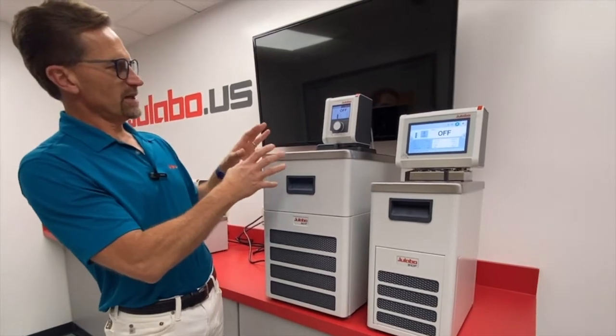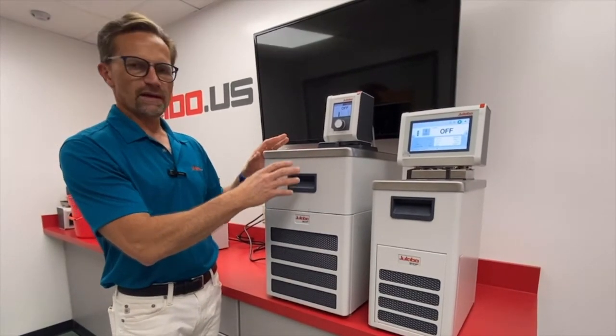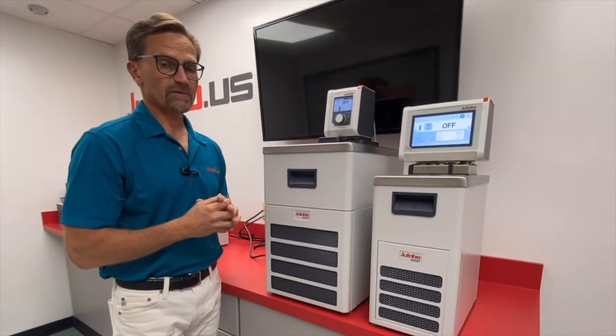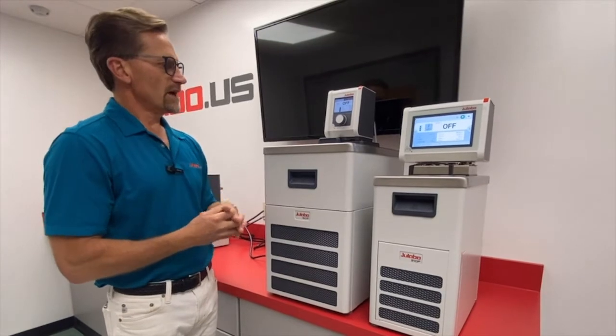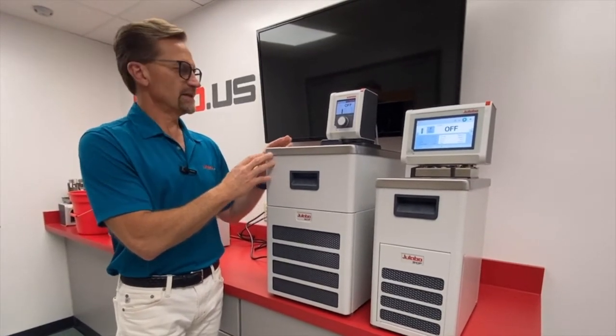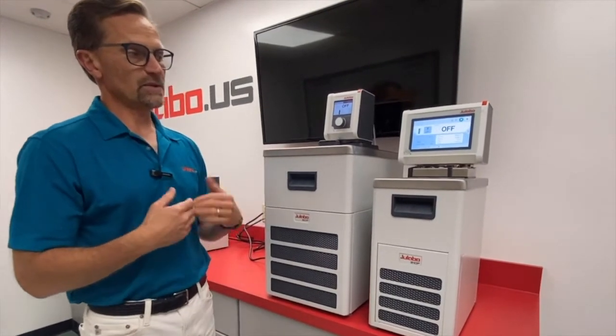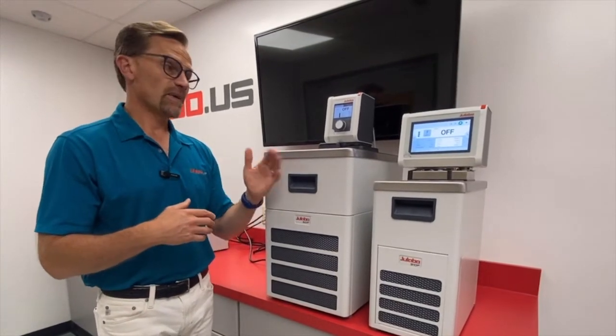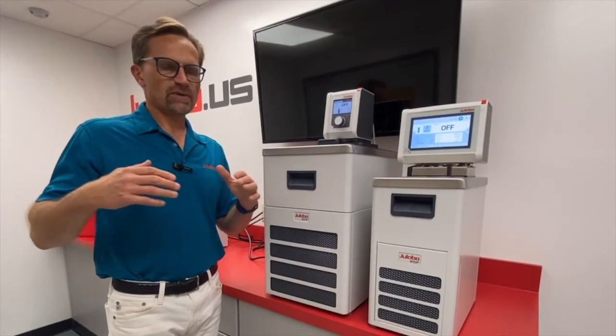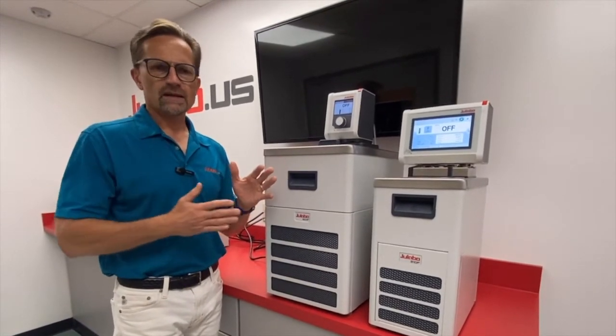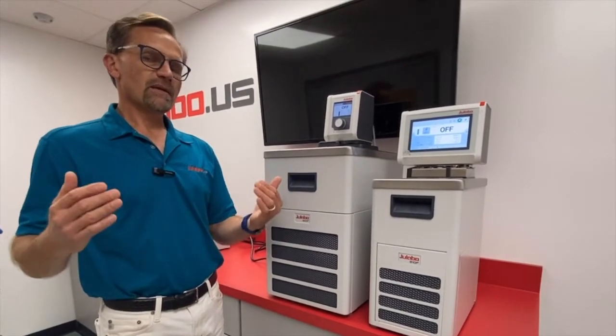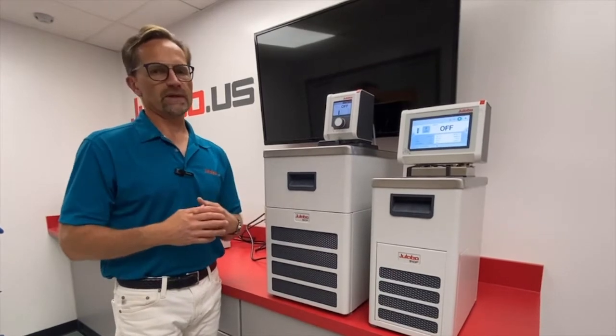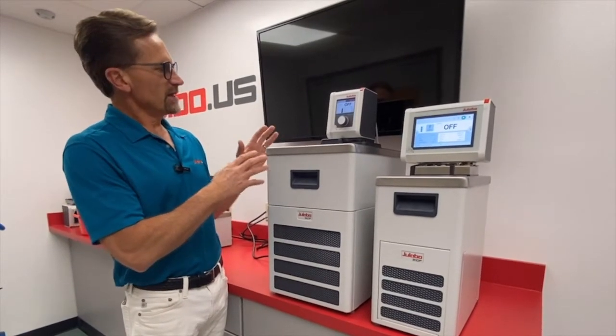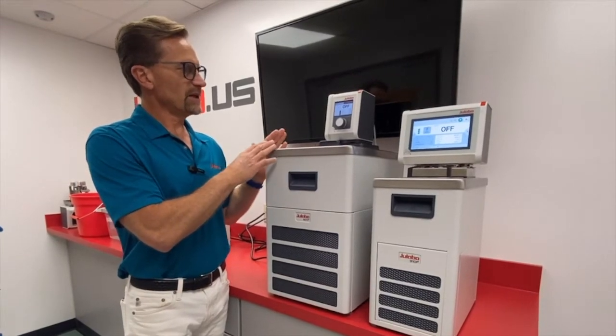From a usability perspective as well, both units are multilingual. They're programmable. You can save up to 8 different programs with 60 steps each. So from a calibration perspective, the DYNEOs can be calibrated with 1, 2, or 3 points, whereas on the MAGIO units, you can do a calibration of 1, 2, or up to 10. So the MAGIO has a better calibration capability. For example, if you have a very broad temperature range that you'd want to do a calibration curve for, having 10 points gives you a much closer fit to that curve than just the 3-point. Okay. In addition, from a stability perspective, both systems have a plus or minus 0.01 degree temperature stability.